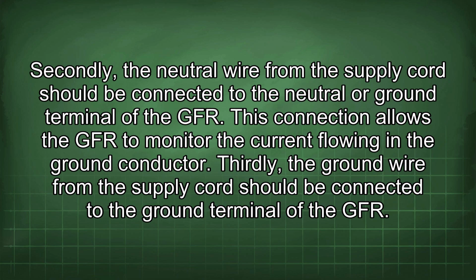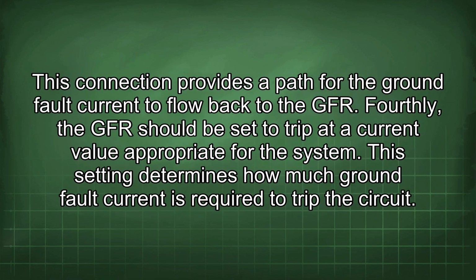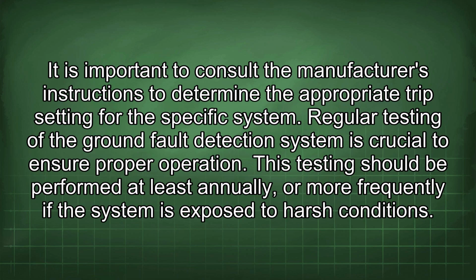Secondly, the neutral wire from the supply cord should be connected to the neutral or ground terminal of the GFR. This connection allows the GFR to monitor the current flowing in the ground conductor. Thirdly, the ground wire from the supply cord should be connected to the ground terminal of the GFR. This connection provides a path for the ground fault current to flow back to the GFR. Fourthly, the GFR should be set to trip at a current value appropriate for the system. This setting determines how much ground fault current is required to trip the circuit. It is important to consult the manufacturer's instructions to determine the appropriate trip setting for the specific system.